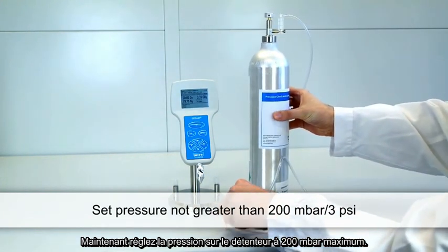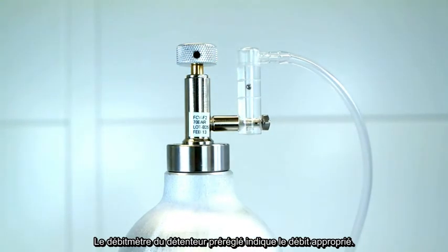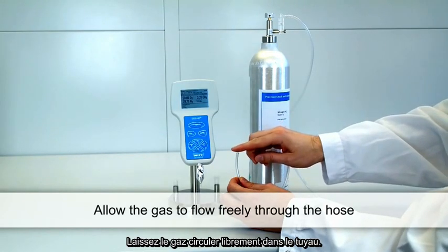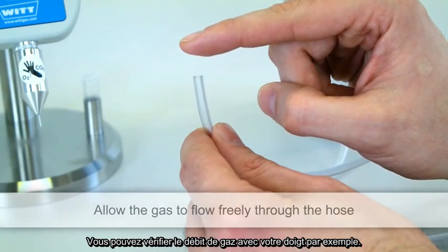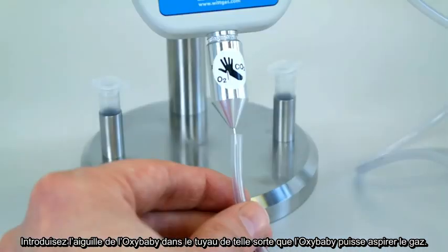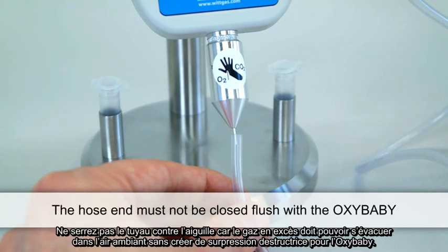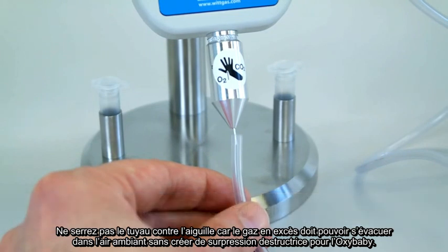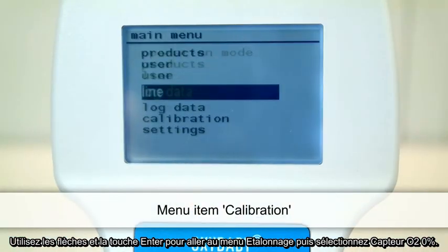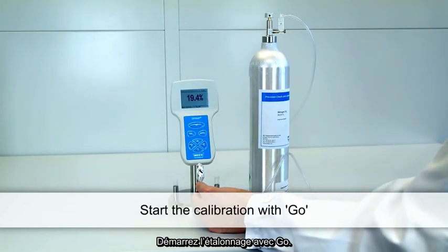The flow meter of the WITT calibration gas set shows the appropriate flow rate. Allow the gas to flow freely through the hose — you may test the flowing gas with your finger. Insert the OxyBaby needle into the hose so that the OxyBaby can acquire the gas. Make sure that the hose end is not closed flush with the OxyBaby, otherwise pressure could build up and the OxyBaby could be damaged. Use the arrow keys and the Enter key to select the menu item Calibration, then select O2 Sensor Zero Percent. Press the Go button to begin the calibration.